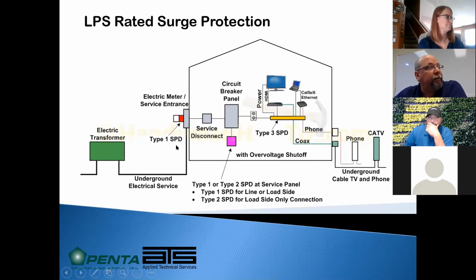A type 1 surge protective device, SPD, is installed at the main electrical service entry, or you can have a type 2 device that's installed on the load side of the service panel. And that protects anything coming in on the underground electrical service. That has to be rated, as I mentioned before, 50% average of lightning strikes is 25 kiloamps. So NFPA and UL require that the type 1 and type 2 surge protective devices be rated at 25 kA.